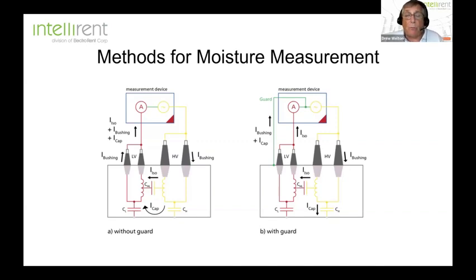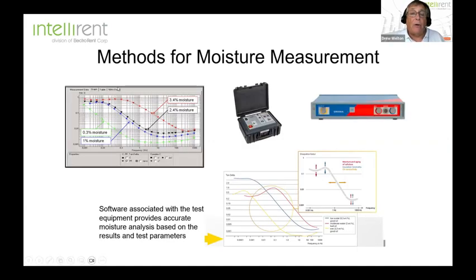It's a very simple test to run. It's one test where they capture the power factor measurement from a very, very low frequency up to a very high frequency, and then plot the curve right here. This is your power factor and this is your frequency. By looking at the geometry of the shape of these curves, you can tell exactly what the moisture content is. There's no super analysis that you would have to do as an operator. The software does that for you. So this is a very accurate test to run.